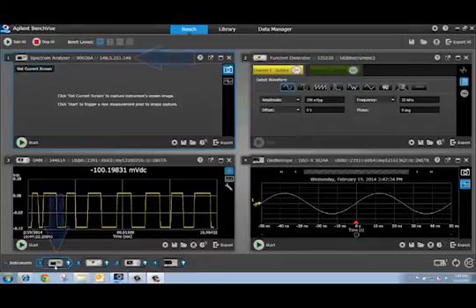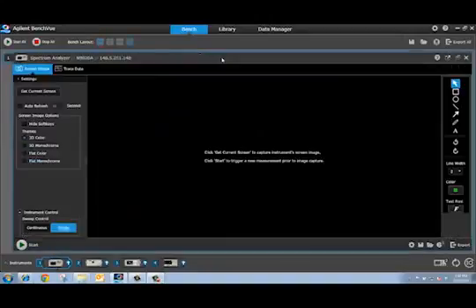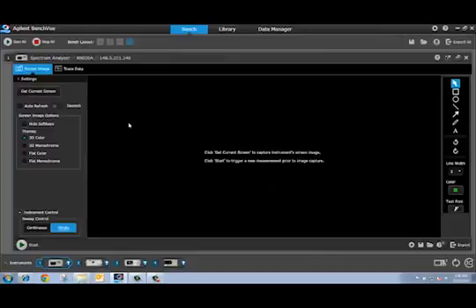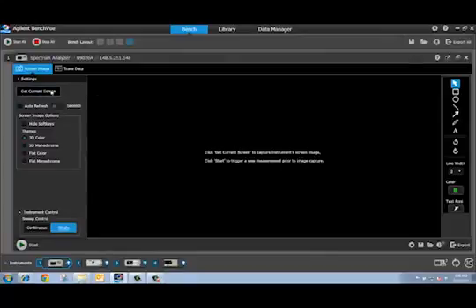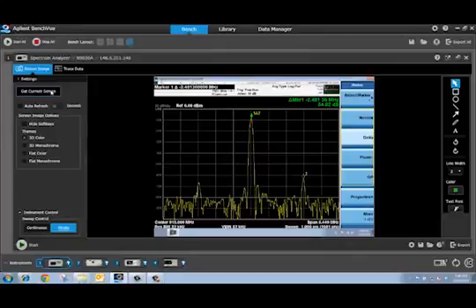So I'm connected to a N9020A MXA signal analyzer. I'm going to bring my signal analyzer Bench application up to full screen and all I have to do is press a single button, get current screen, and I can get a screenshot from my signal analyzer.